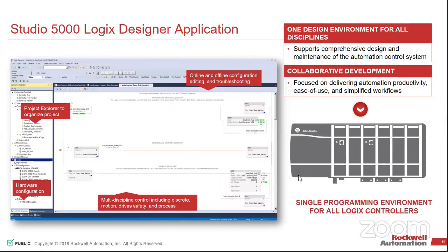As of version 24, we did introduce the Logix organizer. That gives us the ability of doing a lot of library modifications inside of the Studio 5000 world, where we can copy and paste pieces of the code and any dependencies, the UDTs and AOIs that existed. The big example we used to use is if you have a boiler 1, you want to make a copy and make a boiler 2. All you have to do is copy that over, and all the tags that existed for it got moved over. That was something they introduced in version 24.